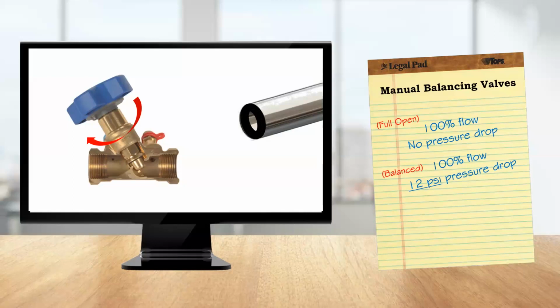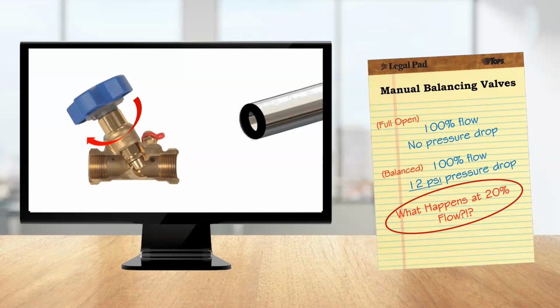So if at 100% flow this smaller opening creates a 12-pound pressure loss, what happens at 20% flow? How much pressure loss is created if it's only at that 20%? Is that smaller opening large enough to accommodate 1/5 of the flow without creating a 12-pound pressure drop? Absolutely. So systems are balanced at a static condition, 100% flow, as we all know. And that means they're only truly in balance at that condition. All other conditions have potential for pressure balancing issues.